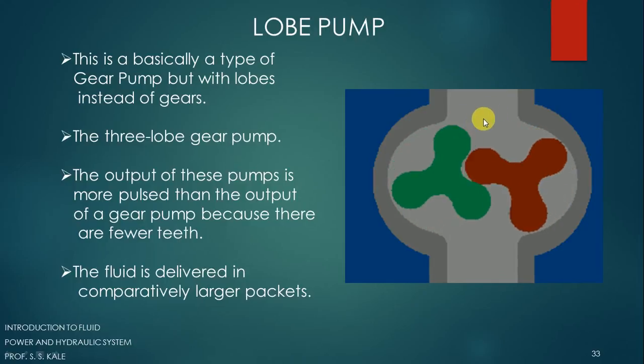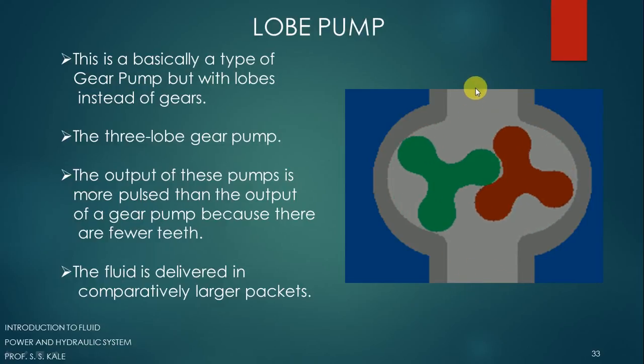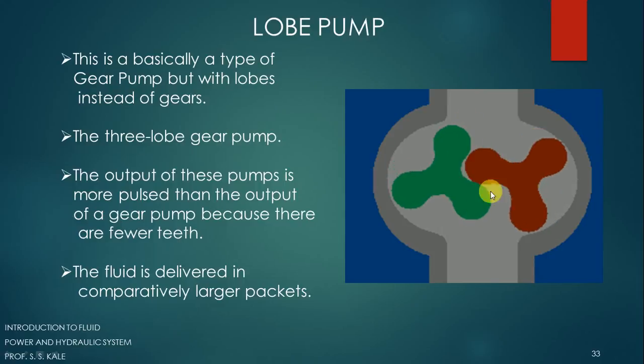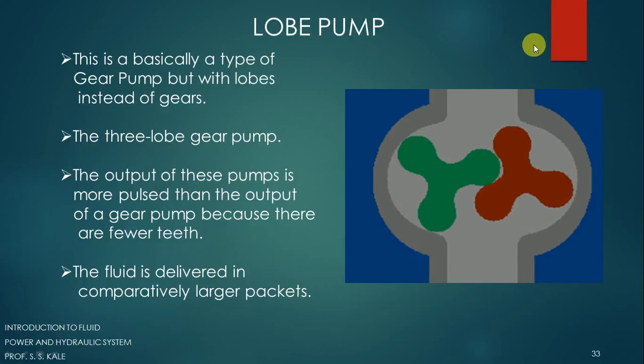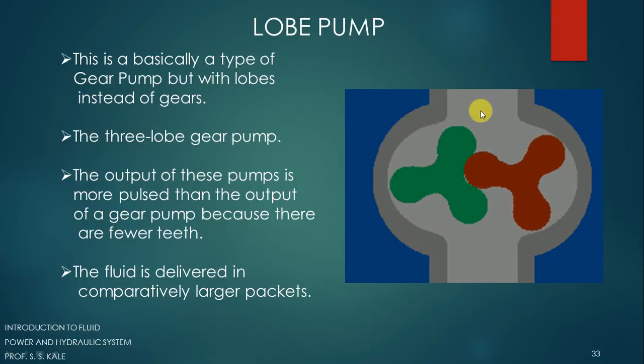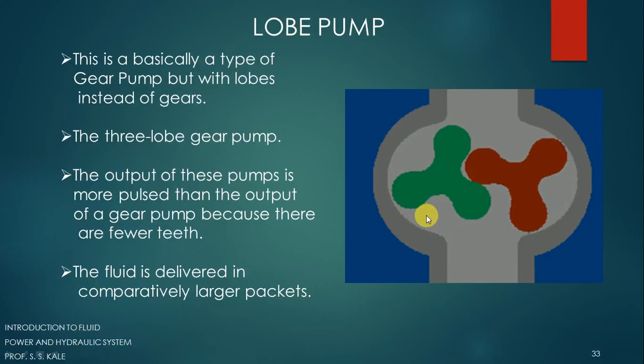Initially there may be no oil present — only air. The air present is first trapped between the two lobes and the casing, and gets delivered to the outlet side. After removing all the air from this part, a vacuum is generated. Since vacuum is pressure below atmosphere, and the oil on the inlet side is at atmospheric pressure, the pressure difference causes oil to be sucked into the pump.